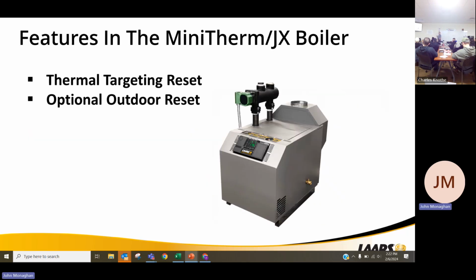So the features in here that I was saying earlier, it has some of the modernized features that are in the more expensive products. It's going to have thermal targeting. Thermal targeting is kind of like, I often refer to it as rate-based reset. It's going to be responding based upon what the indoor temperature is. You get a call for heat, set point of the boiler is looking at 160. Boiler runs for about 15 minutes. Target set point only got to 150. Next call for heat, instead of getting to 160, it's going to get to 155. And it's going to drive itself down to its lowest point where it's not going to be condensing. It'll work its way up to its highest point as well on colder days.